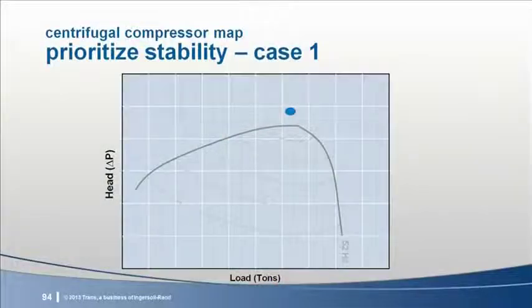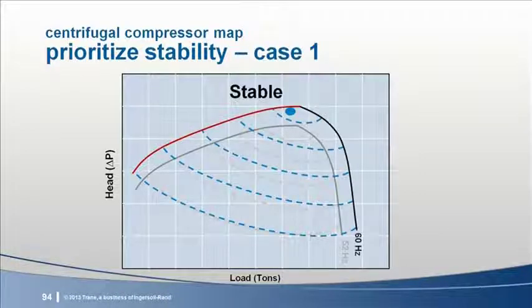a surge condition. Surge is noisy, it scares operators, and it's inefficient, and worst of all, if it's severe enough and continues long enough, it causes damage to the compressor bearings. All in all, this is not a good thing. For this reason, the chiller's controller is programmed to rapidly react to the surge condition, speeding up the compressor to restore stable operation. If the system were operating at its peak efficiency at the previous conditions, then by definition, this is likely a less efficient operating point.